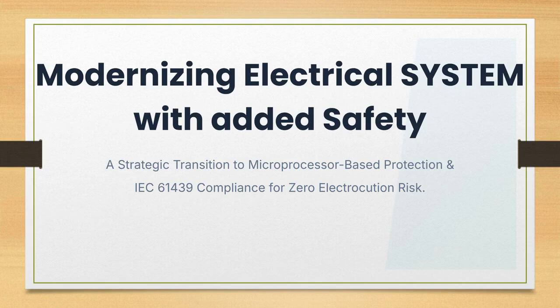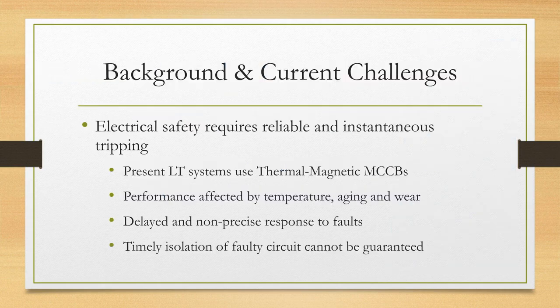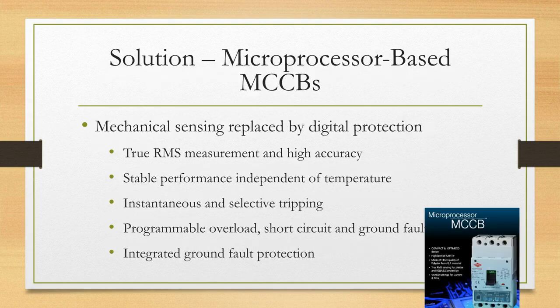This video discusses modernizing an electrical system with added safety, transitioning to microprocessor-based protection, and IEC 61439 compliance for zero electrocution risk. Current challenges in electrical safety include the reliance on thermal-magnetic MCCBs in present low-tension systems. Their performance is affected by temperature, aging, and wear, leading to delayed and non-precise responses to faults. The solution is microprocessor-based MCCBs, which replace mechanical sensing with digital protection.